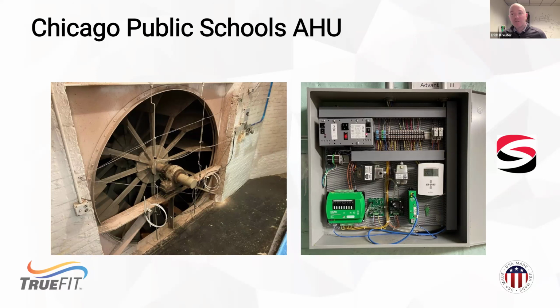To run the AFMS, all the pneumatic control was maintained. We E to P'd the damper signal into the AFMS and then E to P'd it back out. So it's still pneumatically controlled, pneumatic muscle moving the dampers. We're just producing airflow measurement with BACnet and trending it in their front end.